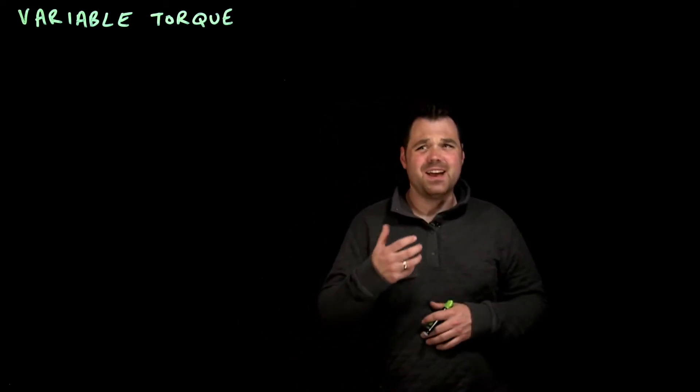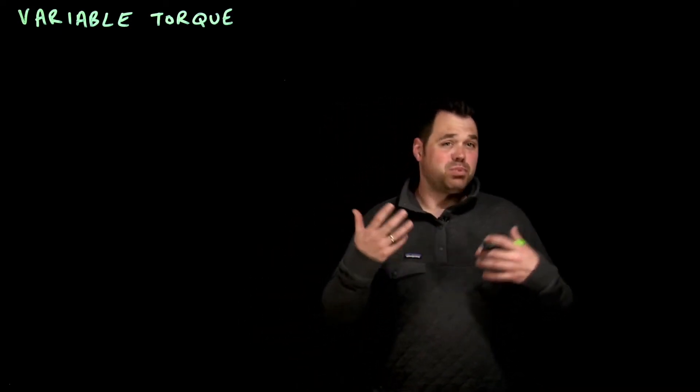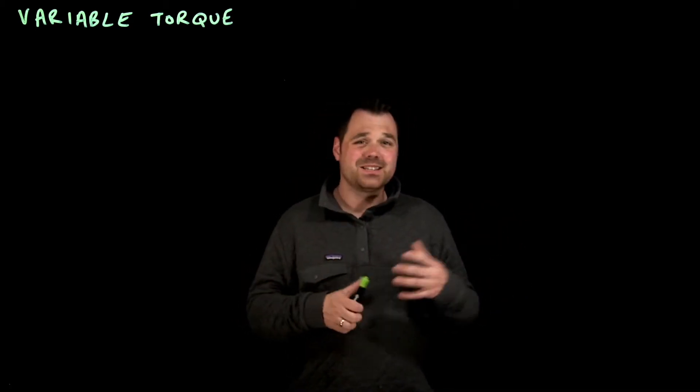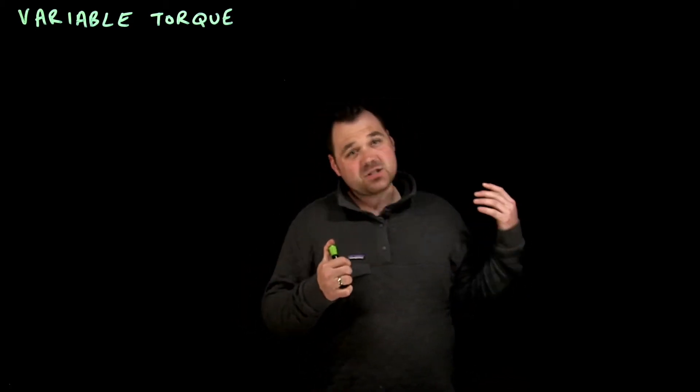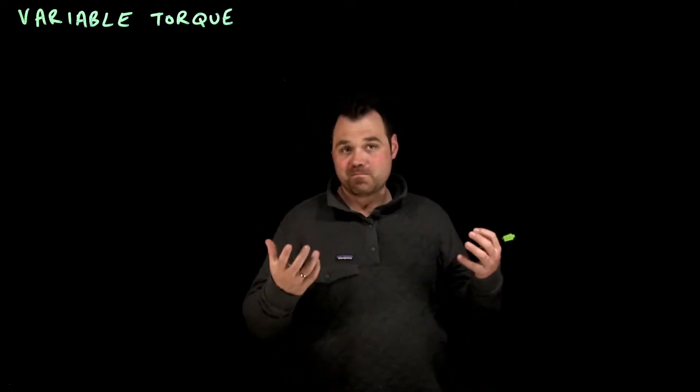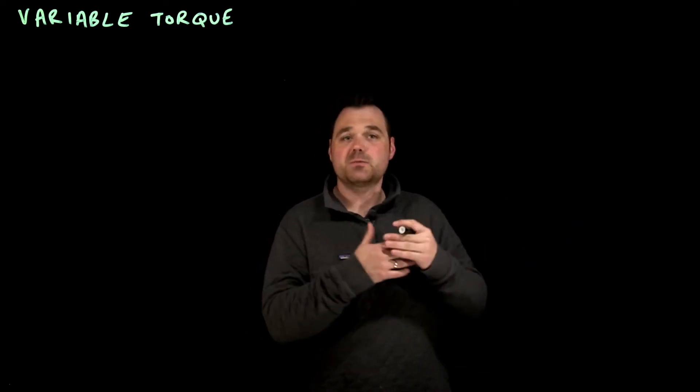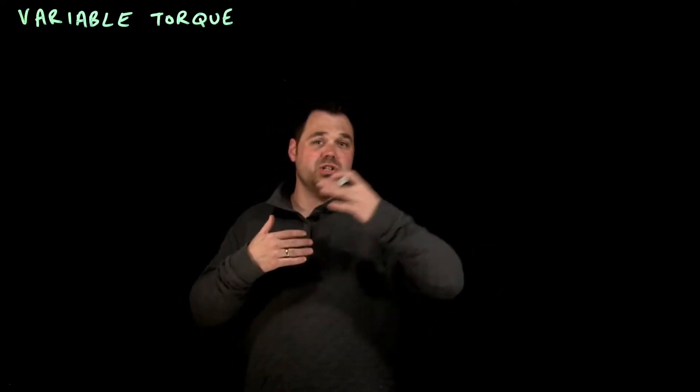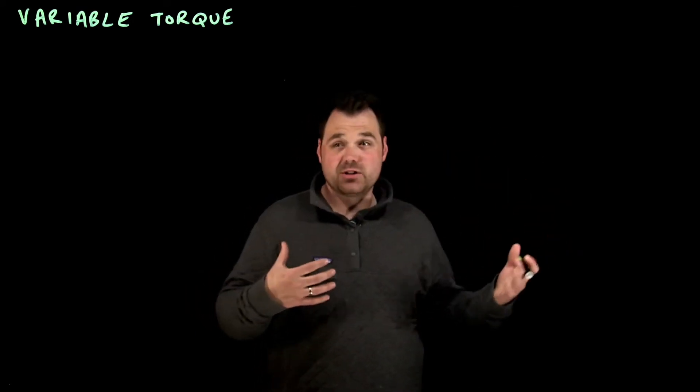I'm talking about variable torque loads. Think about things like cooling fans, exhaust fans, blowers, water pumps for chillers and heaters and things like that. The faster I want to move the air or the water, the more torque I require. So I want to move air fast, lots of torque. If I just want to move air a little bit, just a little bit of torque. The torque changes throughout the operating range of the motor.